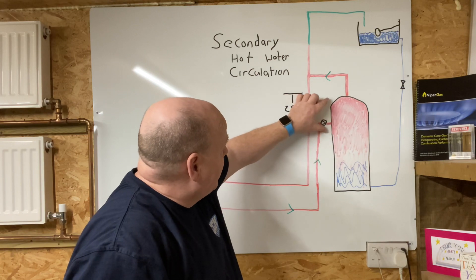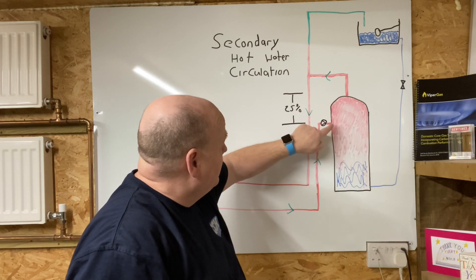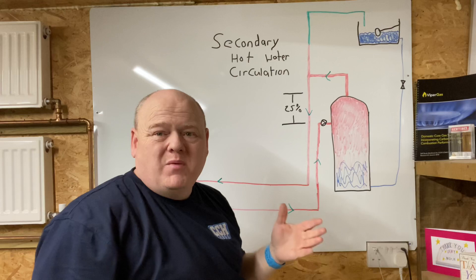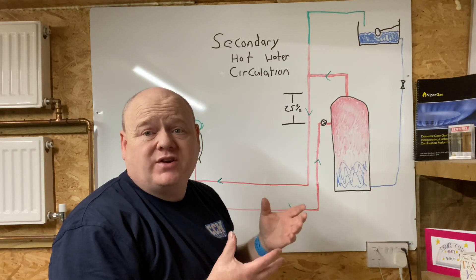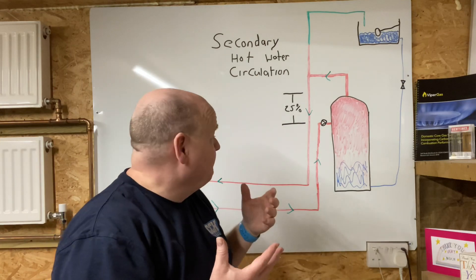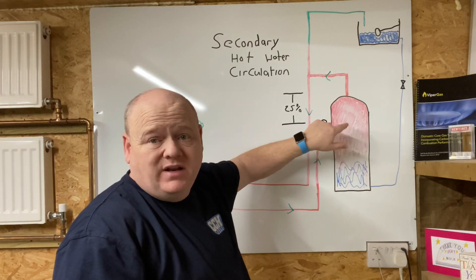The pump or circulator is normally operated by a time clock which only permits water to circulate around the system when the building is occupied, to conserve energy. The secondary return pipe normally includes the installation of a non-return check valve near the pump — not shown here but you normally have one. This connection normally tees back into the cylinder on the return at about 25% down on the cylinder. When you buy an unvented cylinder you'll normally already have the connection point for this.